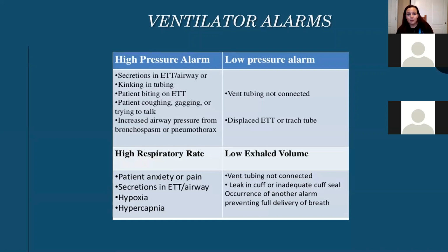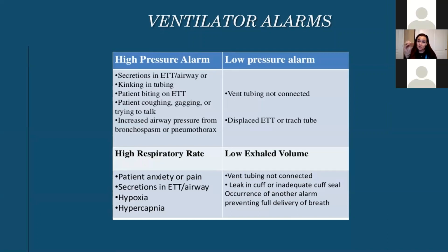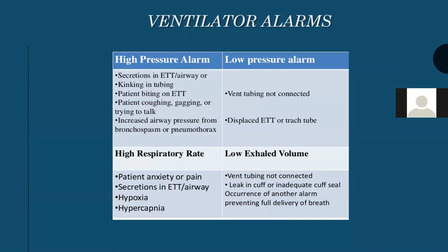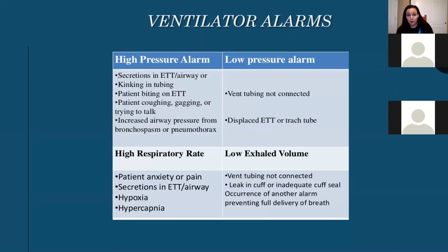So here's a little breakdown of what could be happening with your patient and those high priority alarms. Your high pressure alarm. So your vent is trying to push a certain tidal volume or a certain pressure in, and it's not able to do that. So what I tell you is to start at the patient and work your way backwards. If you start at the end of your ET tube, what could be happening down there is a compliance issue. Secondly, what can be happening down there is secretions. For a compliance issue, you're going to have to mess with the ventilator. For secretions, you're going to have to suction your airway out.